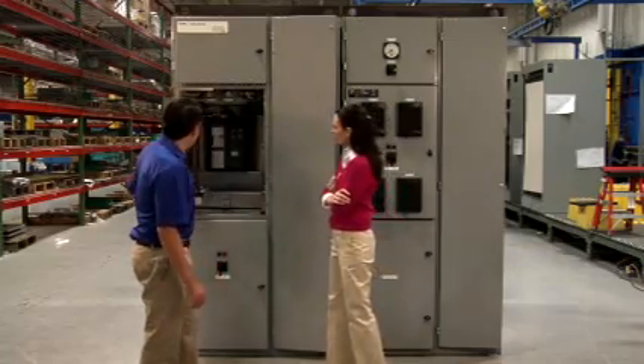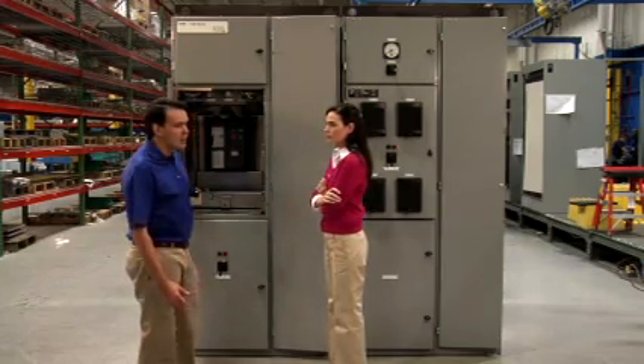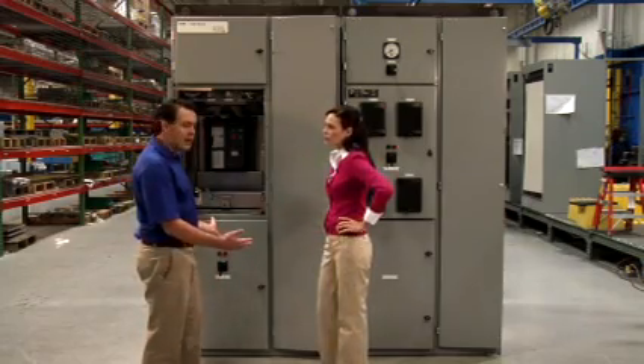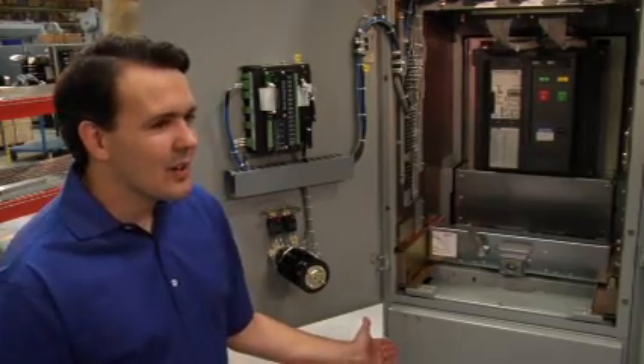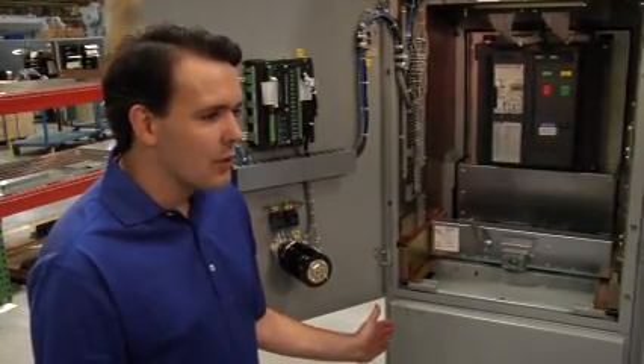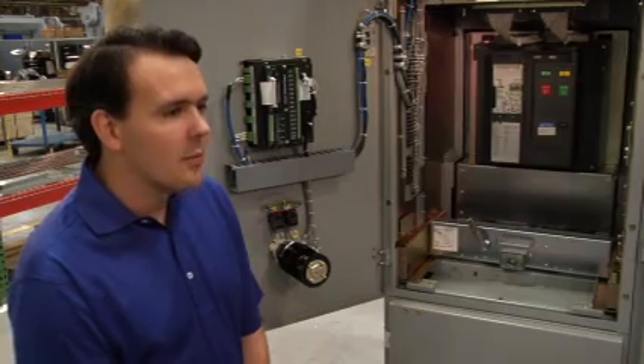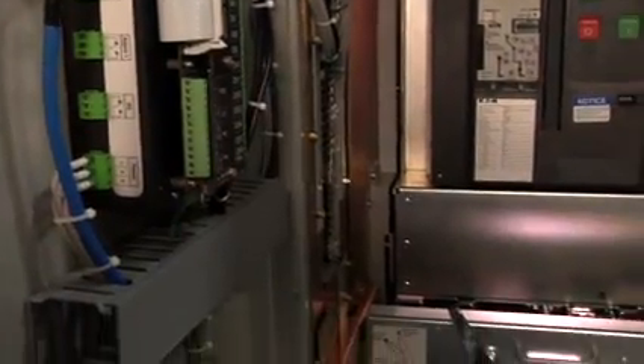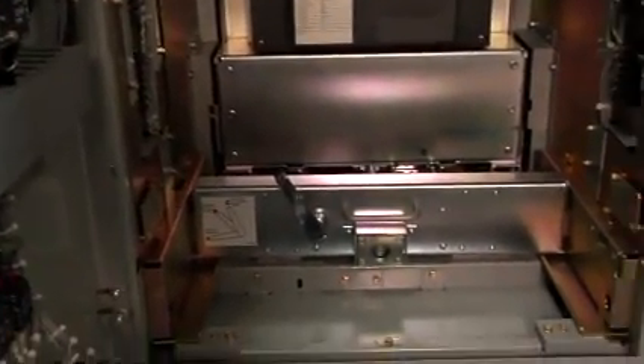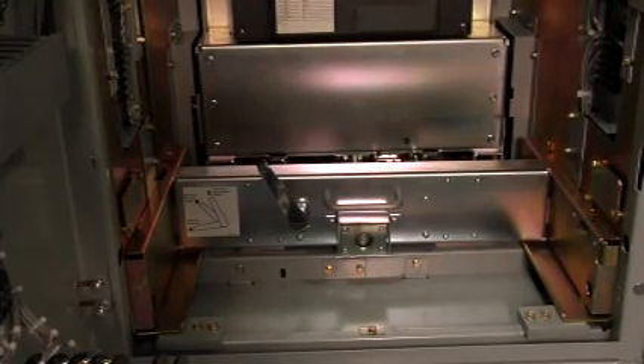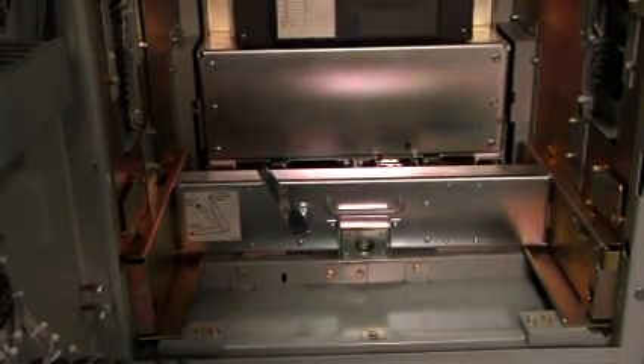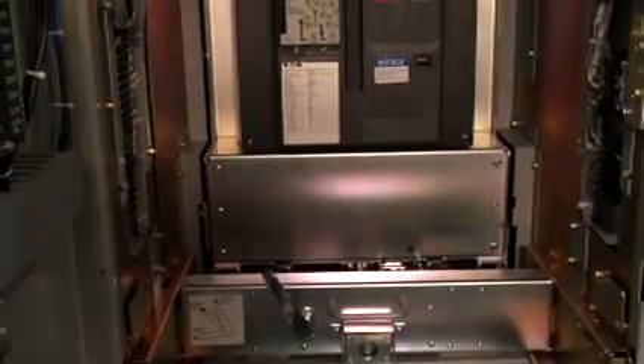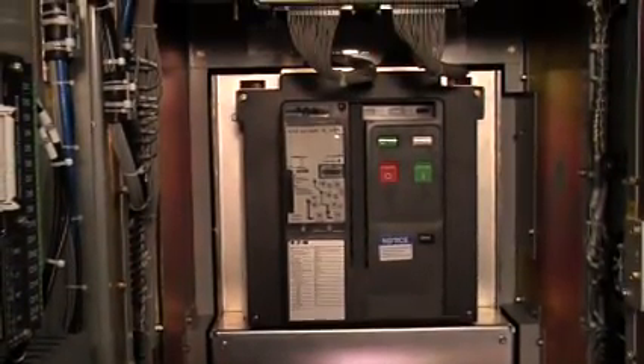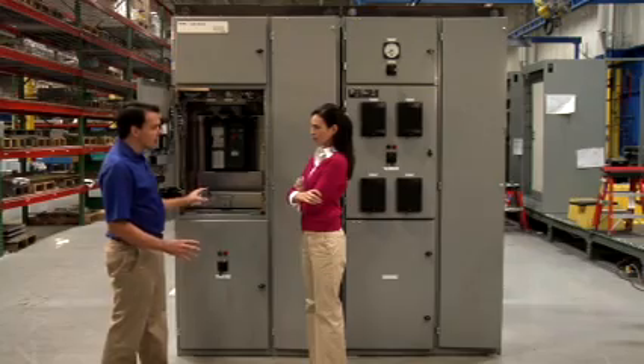Okay, it's small, it's light, it corners well, but what do we have under the hood? All of the safety features that you would expect to find in a piece of metal-clad switchgear, you're also going to find in this switchgear. So what we're looking at here is actually a 15,000-volt power circuit breaker with 40K interrupting capability. It's actually a withdrawable device. You can notice right off the bat there's a handle here, there's a lever. This is a fully withdrawable breaker, and all these levers and handles are all interlocks to make sure you go through the proper sequence of operations so that when you do withdraw this breaker, you're doing it safely.